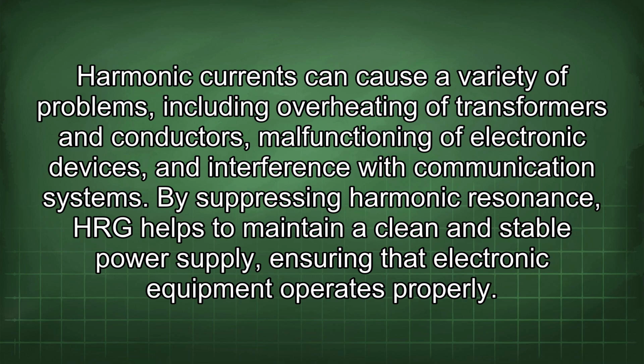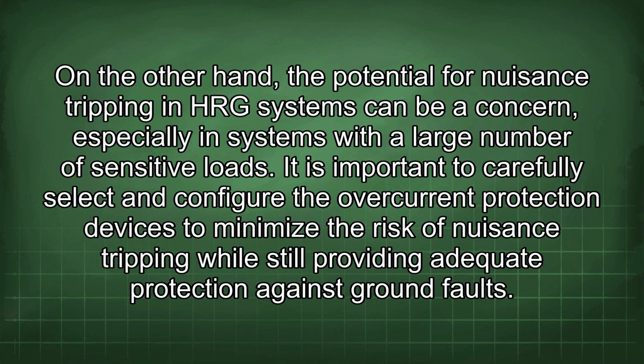By suppressing harmonic resonance, HRG helps to maintain a clean and stable power supply, ensuring that electronic equipment operates properly. On the other hand, the potential for nuisance tripping in HRG systems can be a concern, especially in systems with a large number of sensitive loads. It is important to carefully select and configure the overcurrent protection devices to minimize the risk of nuisance tripping while still providing adequate protection against ground faults.